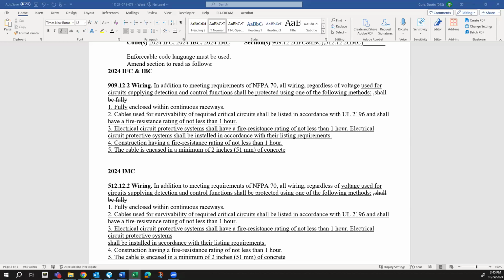But like you said, it was already approved in the 2027 IBC and IFC, correct? And if that's the case, then sooner or later the options will be available anyway for the general population. Yeah, and the NEC has requirements for protection of wire below 7 feet. So you can't just stack up an electrical room, and typically we show everything that's going to be surface run in a continuous raceway anyway, because behind a sheetrock sprinklered building, that's how we look at it as protected. If it's just open cabling in a sprinklered building, that is not what the intent is for it.